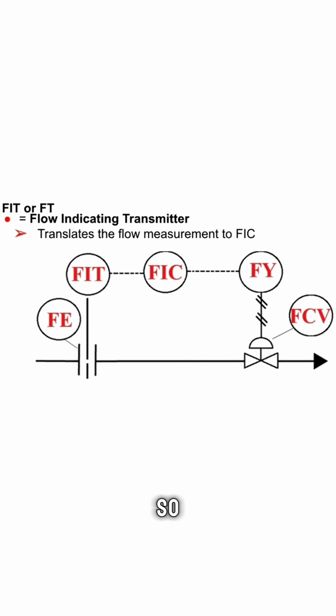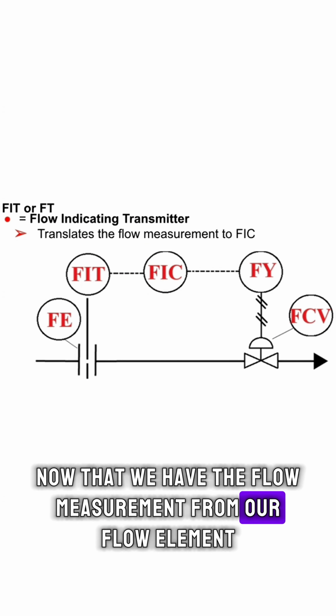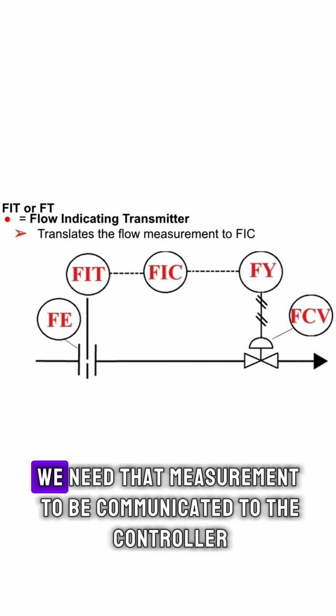So now that we have the flow measurement from our flow element, we need that measurement to be communicated to the controller that is on the board. The FIT, flow indicating transmitter, translates the measurement into an electrical reading and sends the reading to the board, or the controller, which is located on the board.